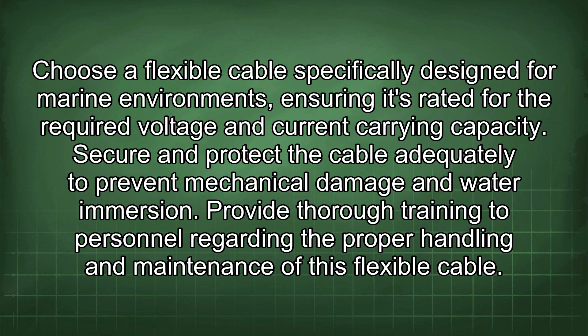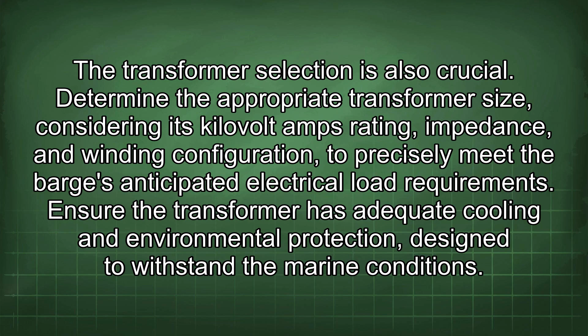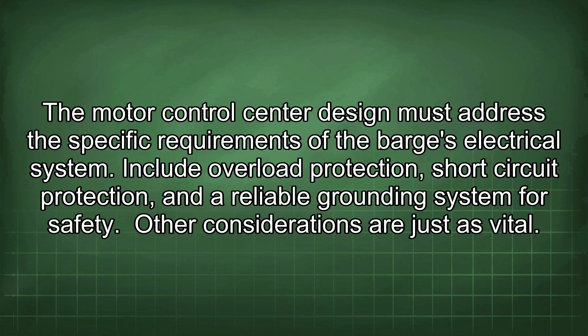The transformer selection is also crucial. Determine the appropriate transformer size, considering its kilovolt amps rating, impedance, and winding configuration to precisely meet the barge's anticipated electrical load requirements. Ensure the transformer has adequate cooling and environmental protection, designed to withstand the marine conditions. The motor control center design must address the specific requirements of the barge's electrical system. Include overload protection, short-circuit protection, and a reliable grounding system for safety.